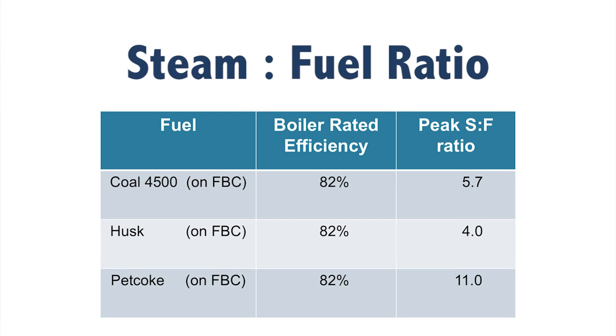Can the gap be bridged? One benchmark that is used to measure the efficiency is the steam to fuel ratio. The steam to fuel ratio is the most practical method of working out the boiler efficiency. Steam to fuel ratio is simply the ratio between the steam generated to the fuel burnt. The higher the steam to fuel ratio, the higher is the boiler efficiency.